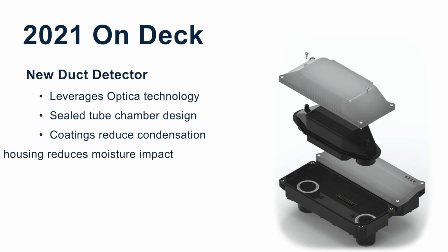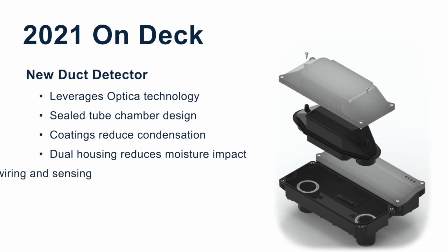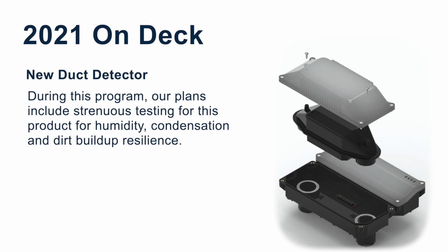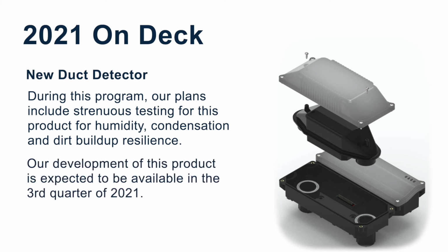These enhancements are combined with a dual compartment design, each with its own cover to prevent condensation due to temperature differentials in and outside the unit. The optic tube is removable and replaceable and can be easily cleaned. There's a separate section with more room for wiring connections. This section is separate with its own cover so that it won't be influenced by air temperature in the sensing tube. This section also contains the unit's status LEDs. So as you can see, we are making great efforts to reduce some of the common issues we've seen in the past with duct detectors. During this program, our plan includes strenuous testing for this product for humidity, condensation, and dirt buildup resilience. Our development of this product is expected to be available in the third quarter of 2021.